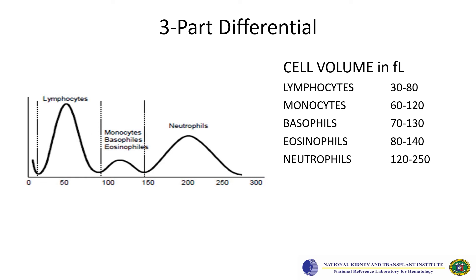A histogram generated in a three-part differential shows the smallest cells — lymphocytes — on the left, with monocytes, basophils, and eosinophils in the middle sharing a single region or peak, and the largest cells — neutrophils — on the far right. One weakness of this method is that it cannot differentiate monocytes, eosinophils, and basophils. While this information may be sufficient for some laboratories, leukocyte abnormalities could be overlooked without peripheral blood smear examination.